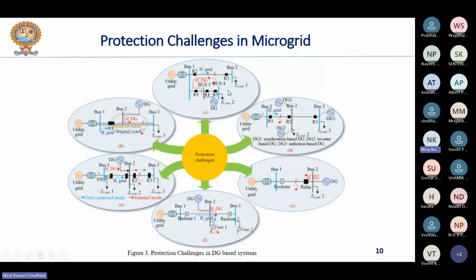So similarly, in the other figures you can see there are problems with the recloser and relay coordination. Then you may have a problem with the recloser coordination. So all these are because of the integration of DG in the system, right? So these are the possible protection coordination challenges. I hope you are aware of this coordination.